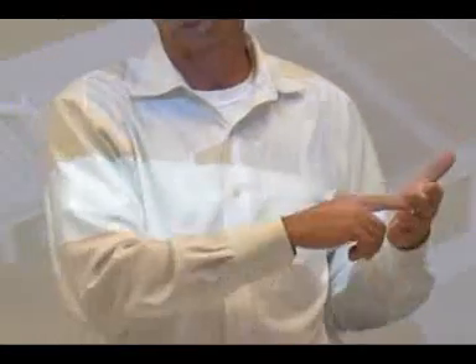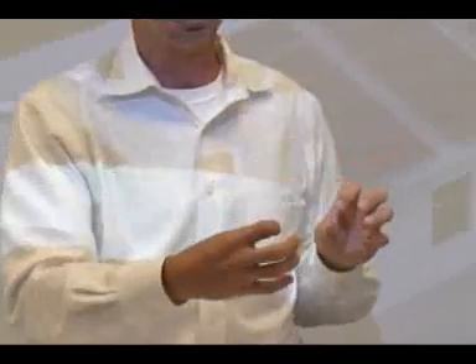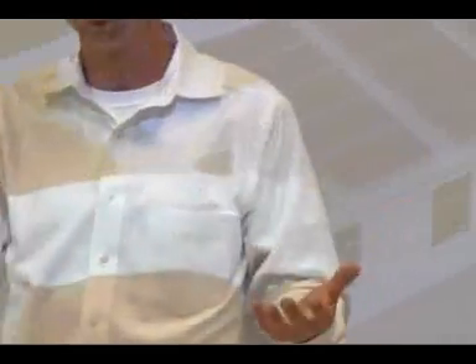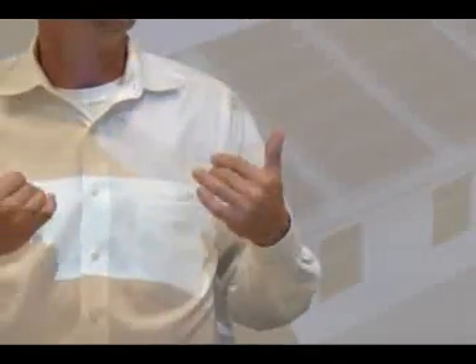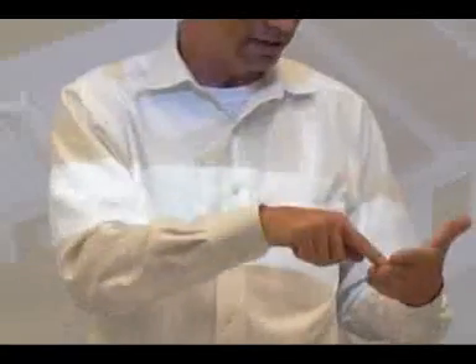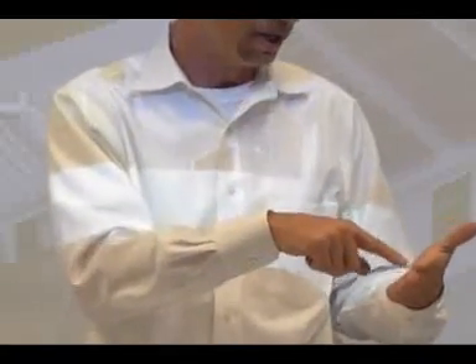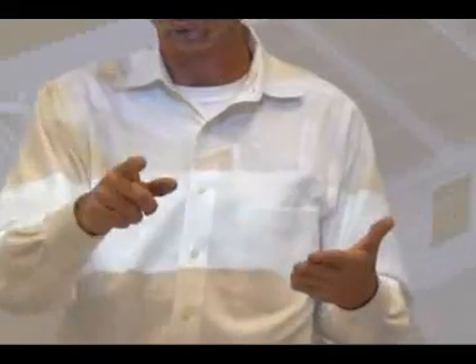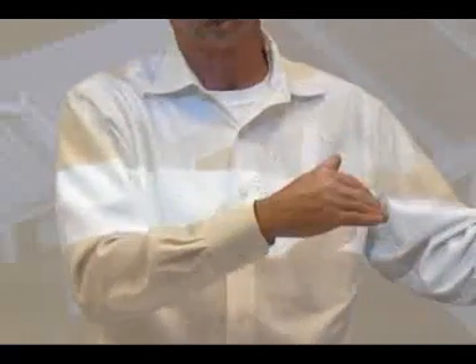And your local utility is going to want to see a paper with a technical line drawing on it explaining exactly what components are in the system, how large the system is, is there a visible lockable disconnect? Because if we do have a storm and our power goes out, the utility company wants that lineman to have a map, and it's going to say a house has a 10K solar system on it. They want him to be able to get out of his truck, walk over there, and pull that handle and disconnect you completely and be able to lock you out of it until they get those power lines restored to service. Once that happens, then you can turn your power system back on.